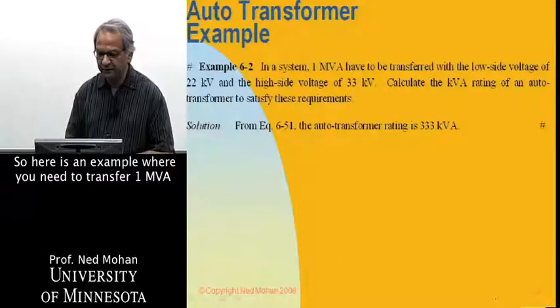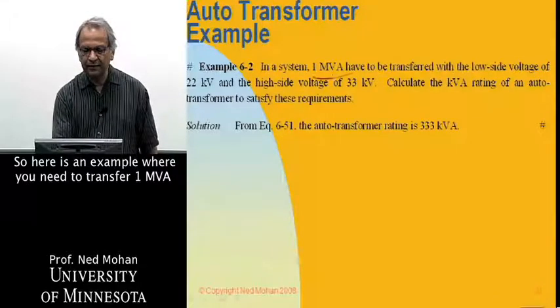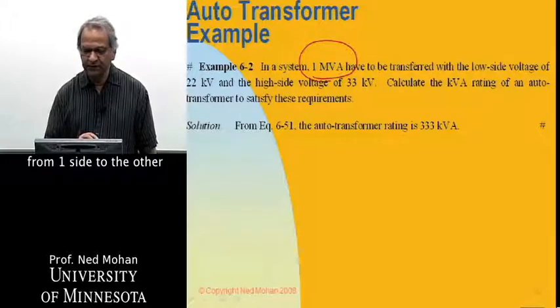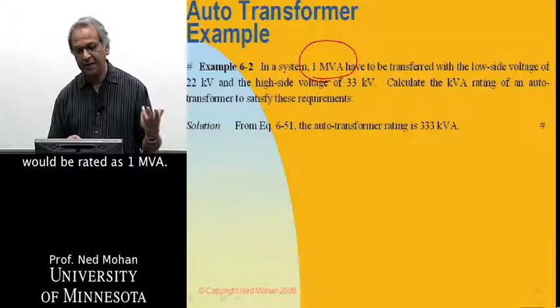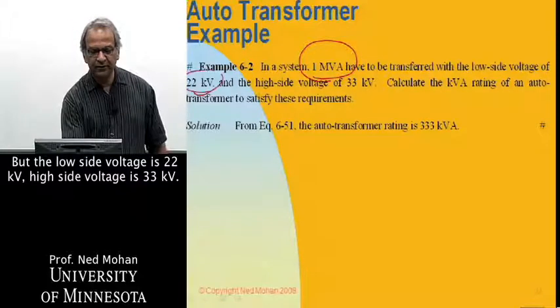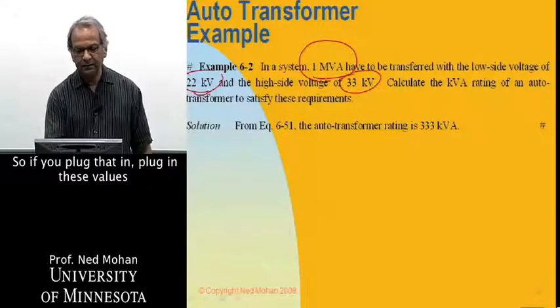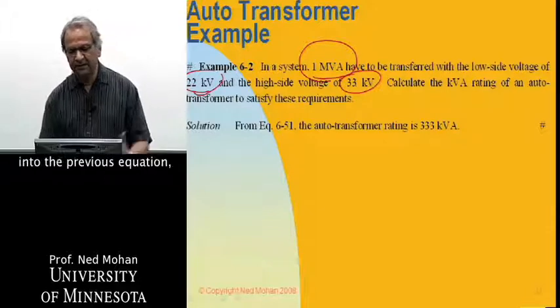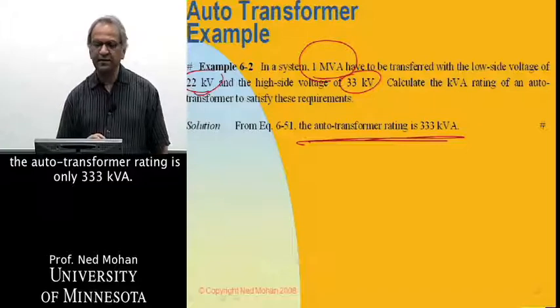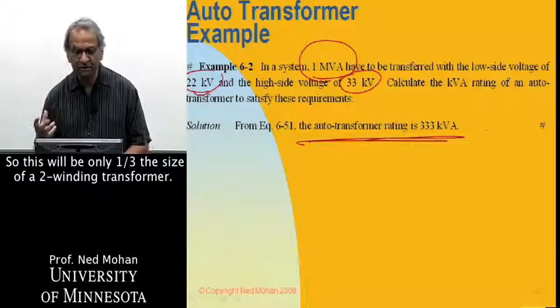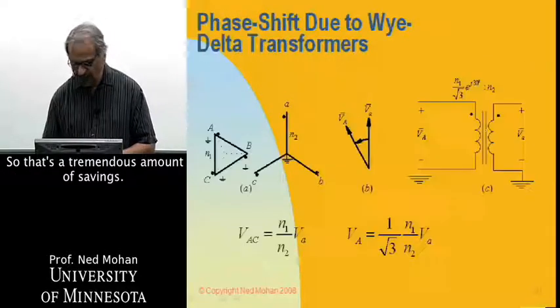So here is an example where you need to transfer one MVA from one side to the other, and if you used a two-winding transformer, your transformer would be rated at one MVA. But the low side voltage is 22 kV, high side voltage is 33 kV. So if you plug that in, the autotransformer rating is only 333 kVA. So this will be only one-third the size of a two-winding transformer. So that's a tremendous amount of savings.